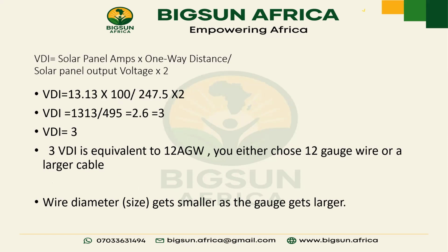The formula for VDI is going to be solar panel amps, which you have gotten to be 13.13, right? Times our one-way distance. What they gave us in the example was 100 feet, right? 100 feet. Then all over the solar panel total voltage, times 2. So our total voltage is 247.5 times 2, right? Which is going to give us what?